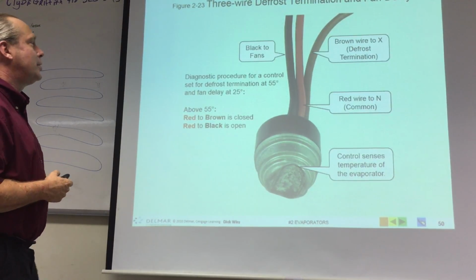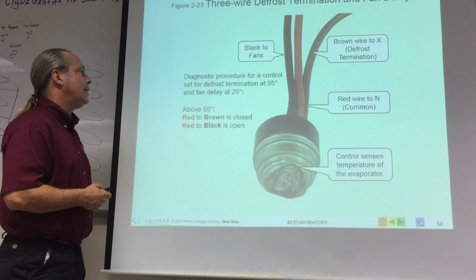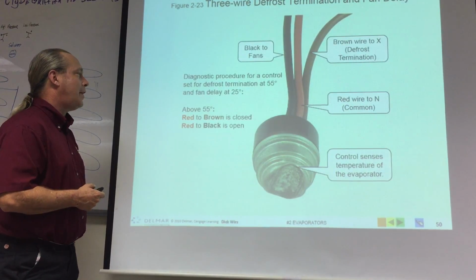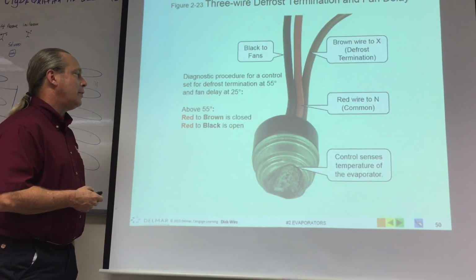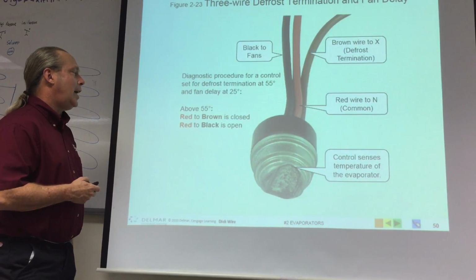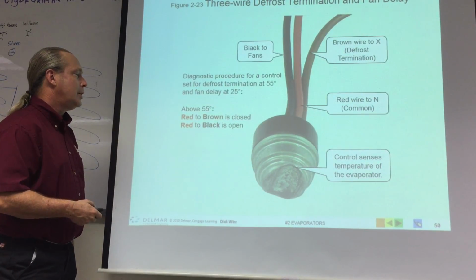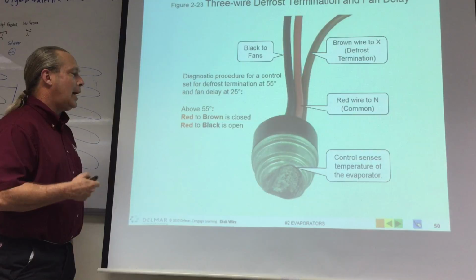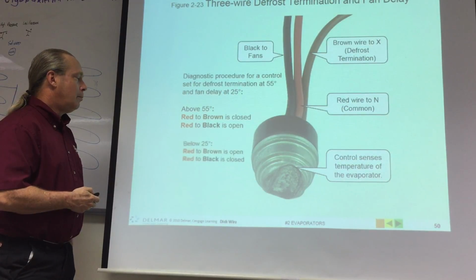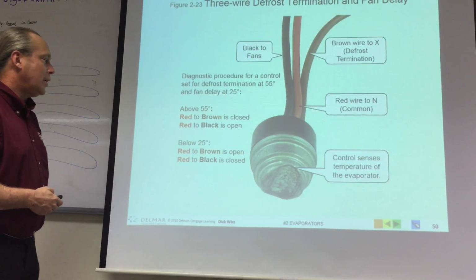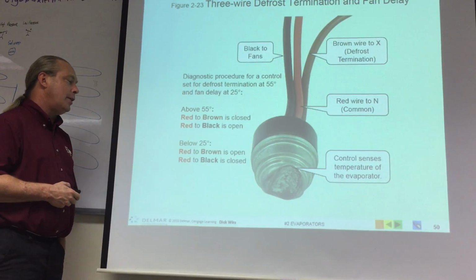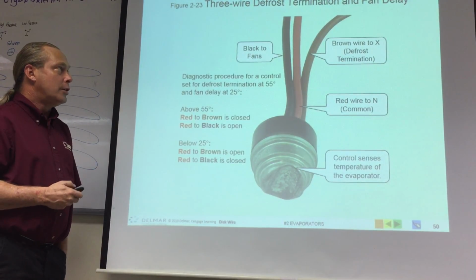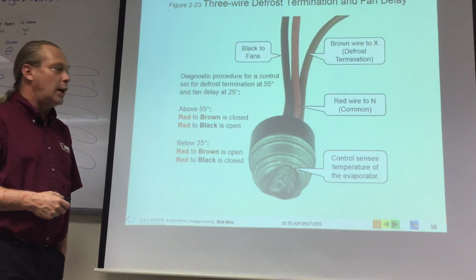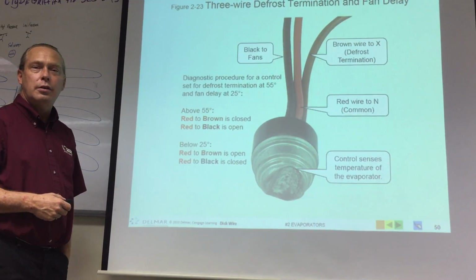The diagnostic procedure for the control is to set for defrost termination at 55 and fan delay at 25. Above 55, red and brown is closed and red and black is open. Below 25, red and brown is open and red and black is closed. So you could diagnose this thing with a cup of ice water, couldn't you?